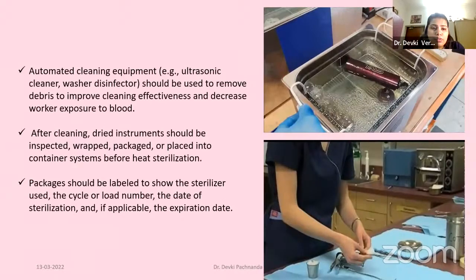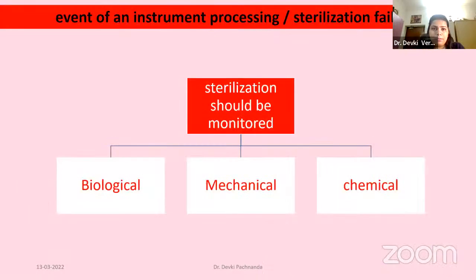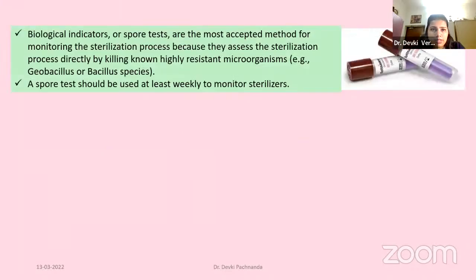area is an area for biofilm formation. Instruments should be wrapped, packed and placed in container systems, and packages should be labeled to show which sterilizer and what cycle, so as to trace back any flaw that happens. Now, what is the event of a sterilization failure, which is where I think the core importance lies. So sterilization can be monitored by biological, mechanical, or chemical methods.